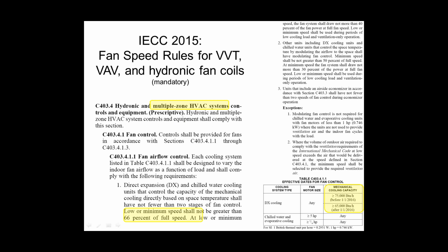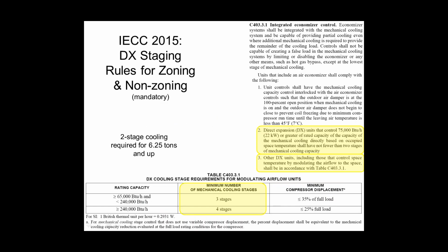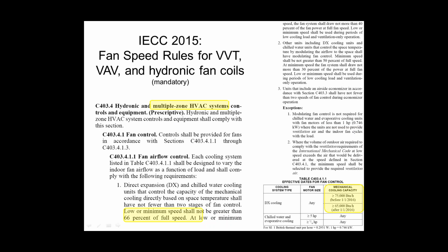You have to have the ability, if you have a 65,000 BTU system or larger, to stage the fan down as well as the cooling system, right? So I go back here, 65,000 BTUs, I got to do 3 stages of cooling and at least 2 stages of fan. I got to throttle the airflow back at least 1/3. So there's been similar versions of this in 90.1.